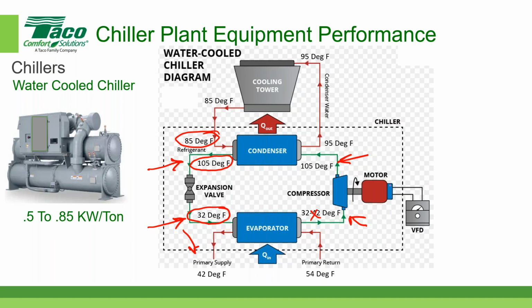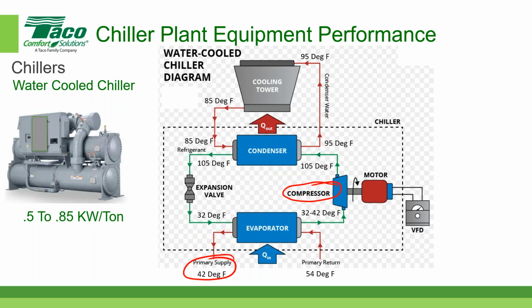So the important thing is that the compressor is trying to raise the refrigerant temperature from 32 in both sides here, from 32 up to 105, and there is a pressure associated with those temperatures. And one last thing I want to point out is that the reason I spend a little extra time talking about this is because conceptually we want to make sure that everybody understands that the amount of work that the compressor has to do is a function of these temperatures, these guys right here.